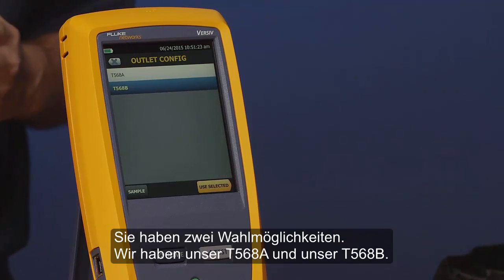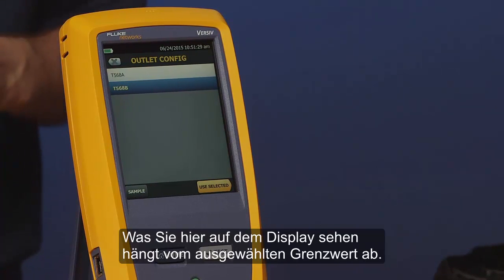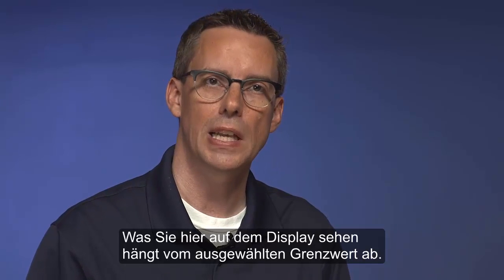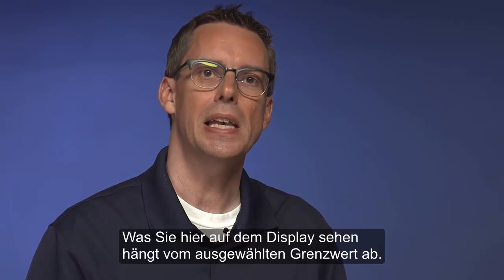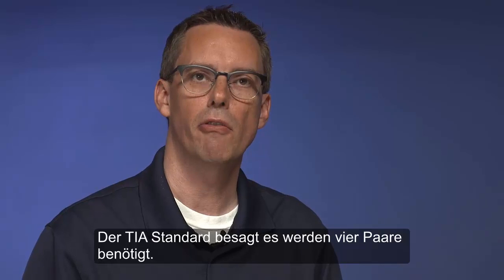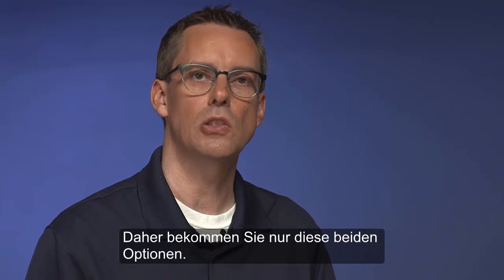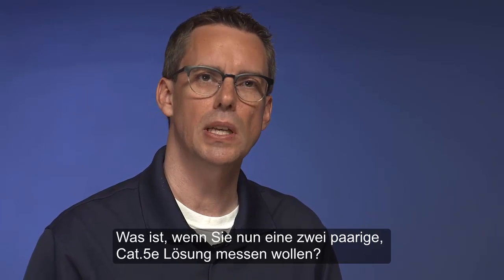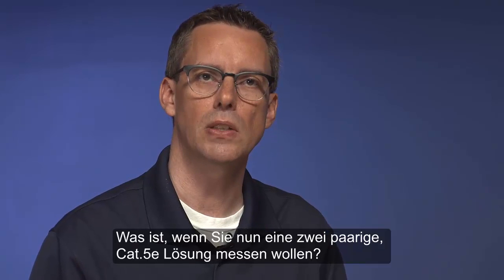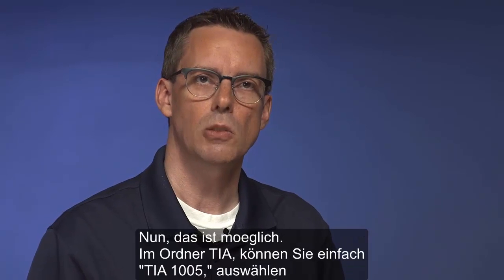You get two choices. We have our T568A and our T568B. What you see on the screen here will be dependent upon what test limit you select. The TIA standard says you've got to have 4 pairs, so you just get these two options. But what if you want to test a 2-pair Cat5e solution? Well, that is possible.